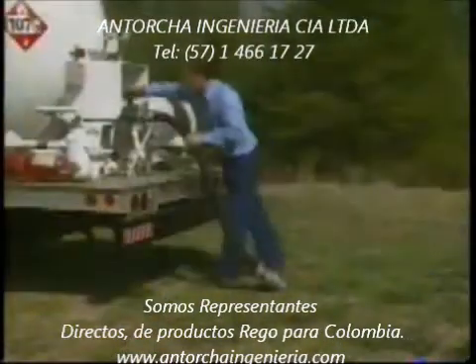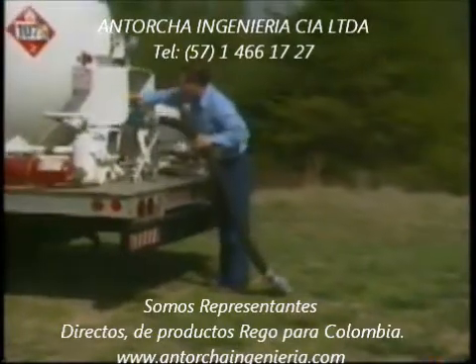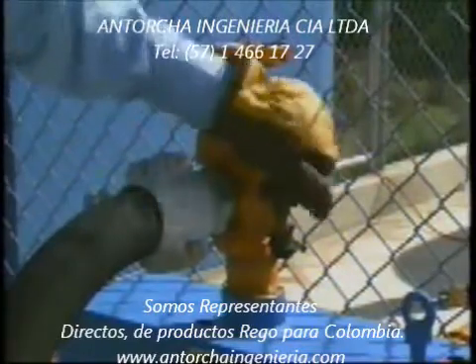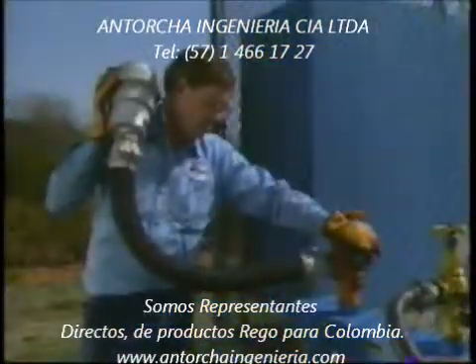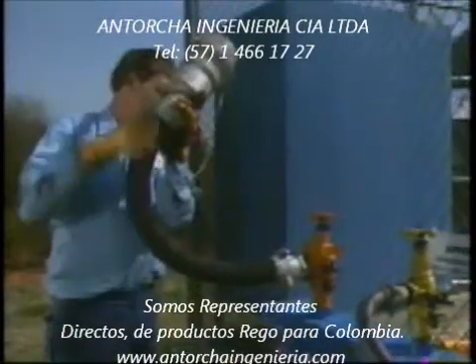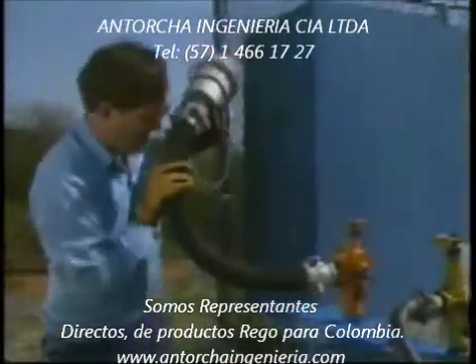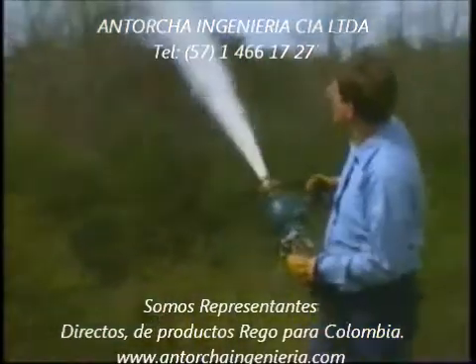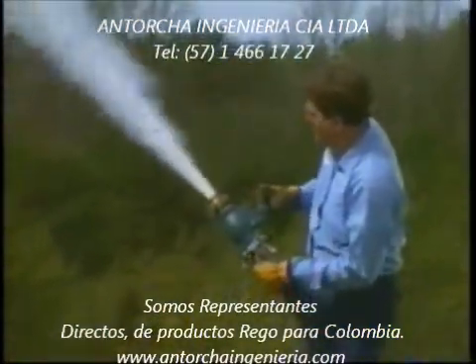The results of an uncontrolled discharge would have been phenomenal. After the valve has separated, it's necessary to release trapped gas from the transfer lines. The pressure is released by turning off the gas supply at the storage container and opening the bleeder valve. The pressure must also be released from the truck end of the line by opening the hose end valve.